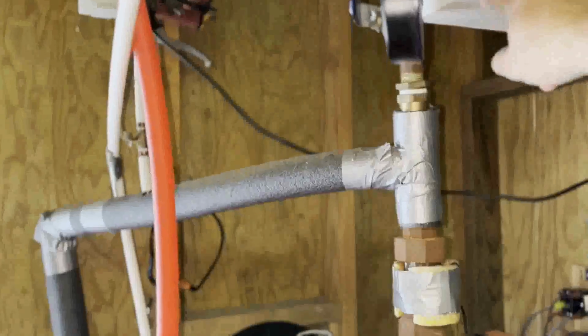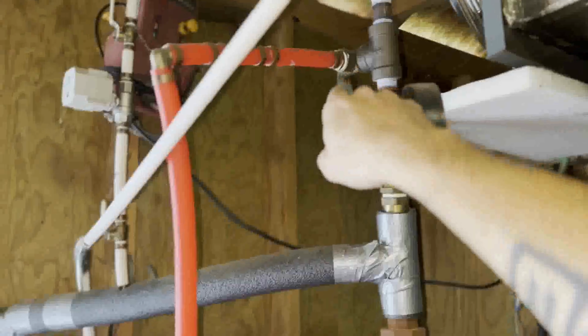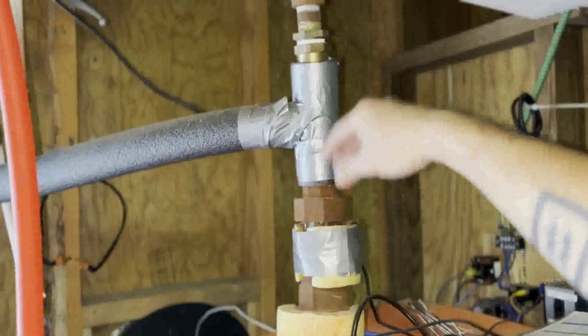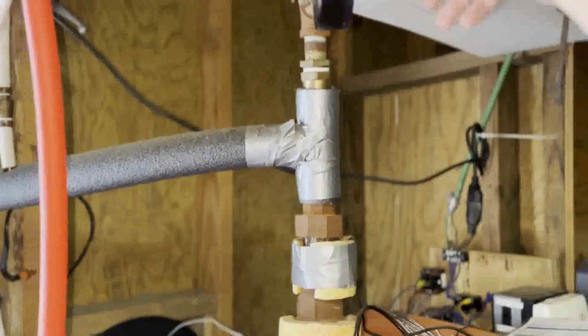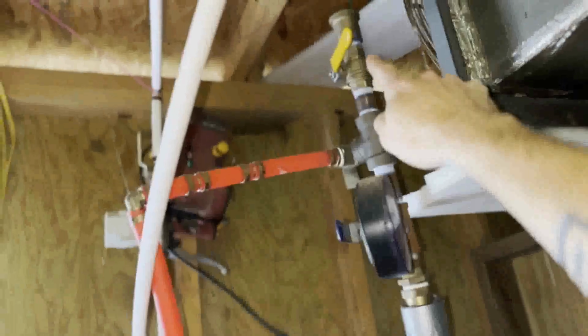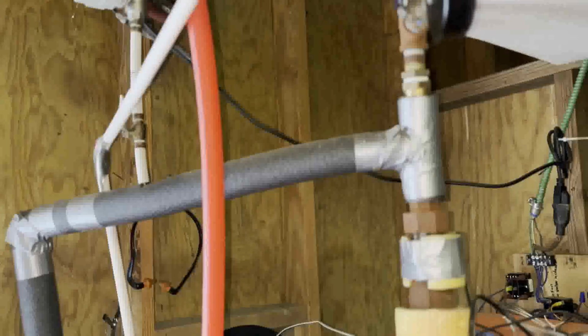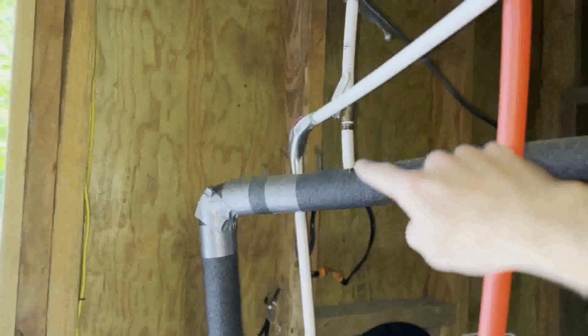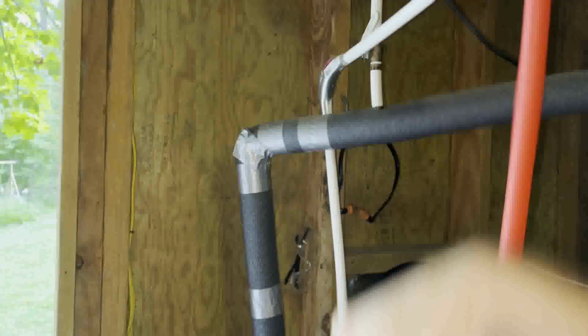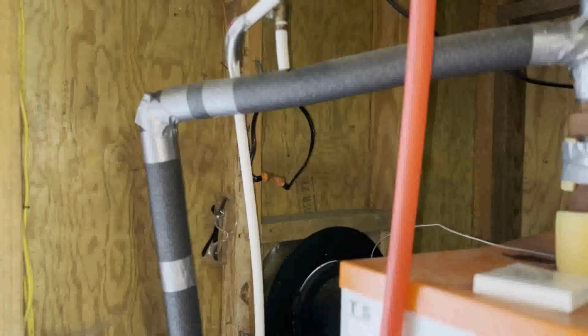But this is not in my house. This is outside, away from my structure where I live. I did want to make that comment. But so we have a pressure relief valve there that just goes down to below this building. It penetrates the floor and goes out. No valves here. You can't have any valves in between the boiler or pressure vessel and your safety relief. That's an air vent here. Once it's bled, it typically is fine. But yeah, so it comes out, the supply comes out, goes down that way, underground. There's two pipes going to the house and back. We'll talk about that a little bit later. But there is a circuit here.